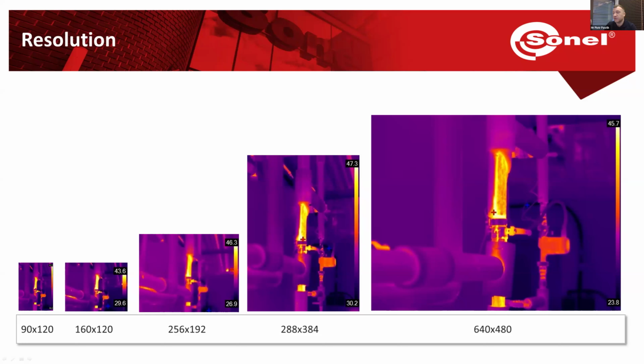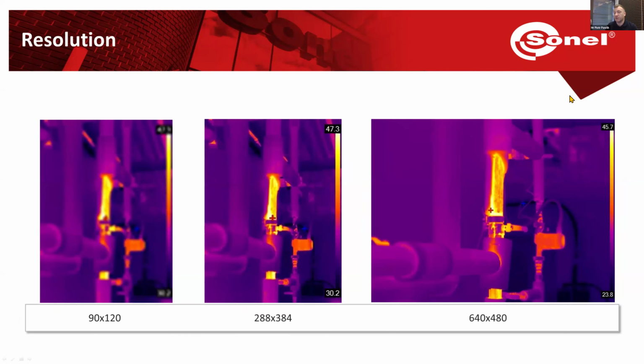And this is also the special feature of thermal imaging cameras, that when we are talking about resolution and detector size, this is the detector that detects the infrared radiation and calculates everything into temperature. Okay, here's another example of different resolution where I extended all the other pictures to be the size of this 640 by 480. So you can see that the smaller pictures, they are just getting blurry once we stretch them.